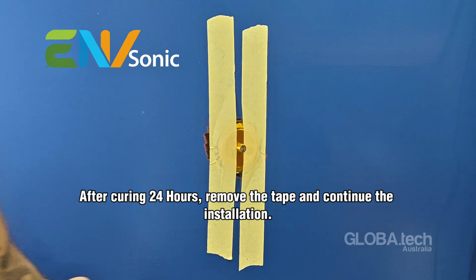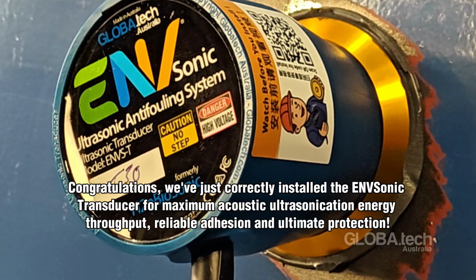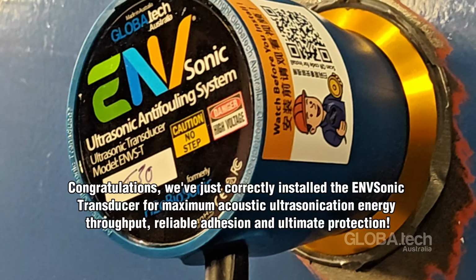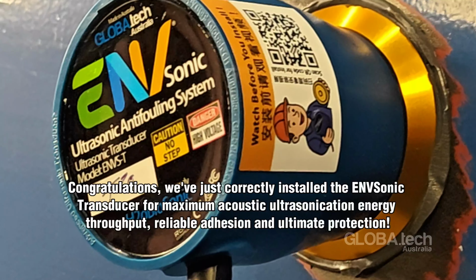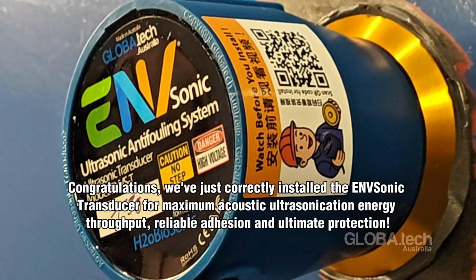It's time to screw the transducer into the mounting footprint. Do this as tight as possible by hand. Leave the Loctite 515 for 24 hours to cure. You can paint the bare steel and carry on with the rest of the install. Congratulations! We've just correctly installed the ENVSonic Transducer for maximum acoustic ultrasonication energy throughput, reliable adhesion and ultimate protection.